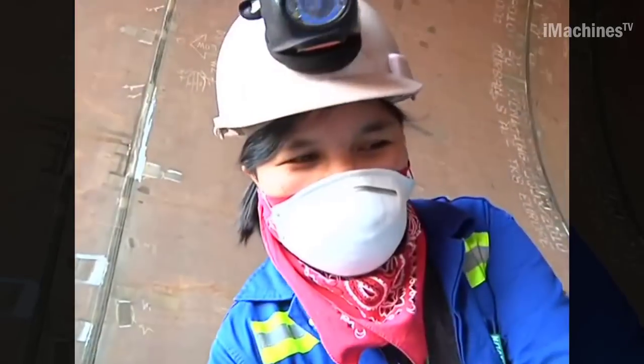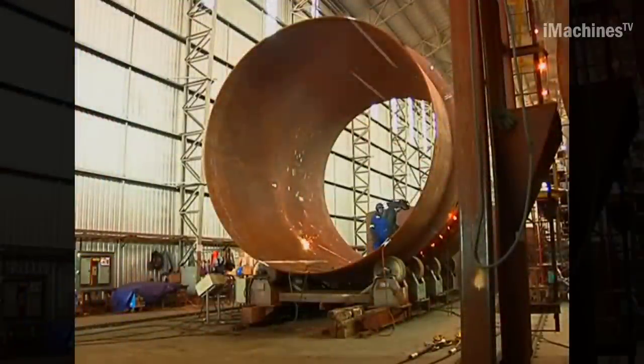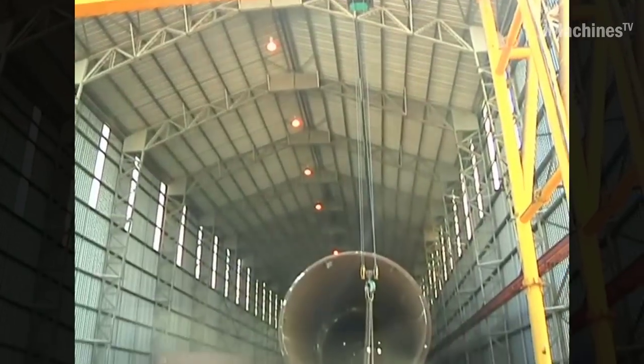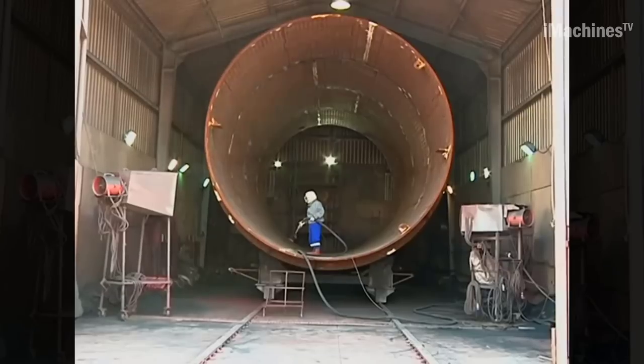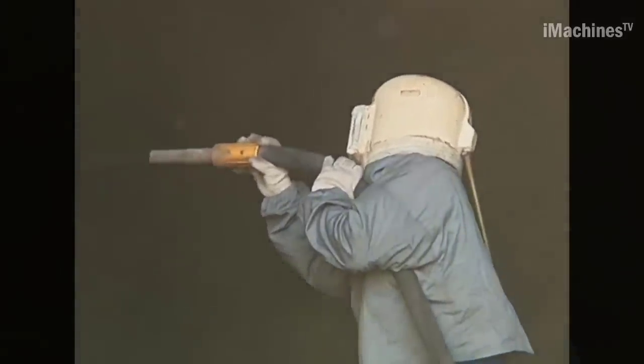With an elevation difference of 470 meters between the upper and lower dams, the water flows to the turbines through low-pressure headrace tunnels and high-pressure inclined shafts. Each tunnel bifurcates into high-pressure penstocks that lead to the turbines. To withstand the high water pressure, the headrace tunnels and inclined shafts are lined with continuous steel linings designed to withstand internal pressures of up to 72 bars.